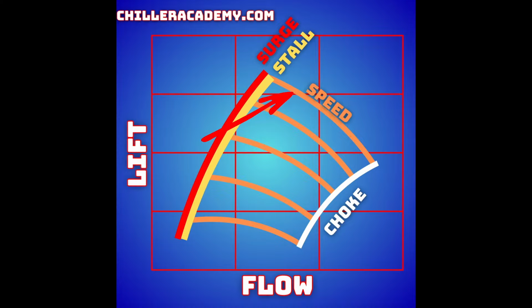Something else that comes into play is if we've got a variable speed machine, as we reduce the speed of the compressor, the amount of lift we can maintain lowers. This is why when a variable speed centrifugal begins to surge, it increases the speed of the motor. Now it may close the inlet guide vanes, but the motor itself will speed up. That is true with any variable speed centrifugal. The reason is because we want to get how much lift we can handle higher.